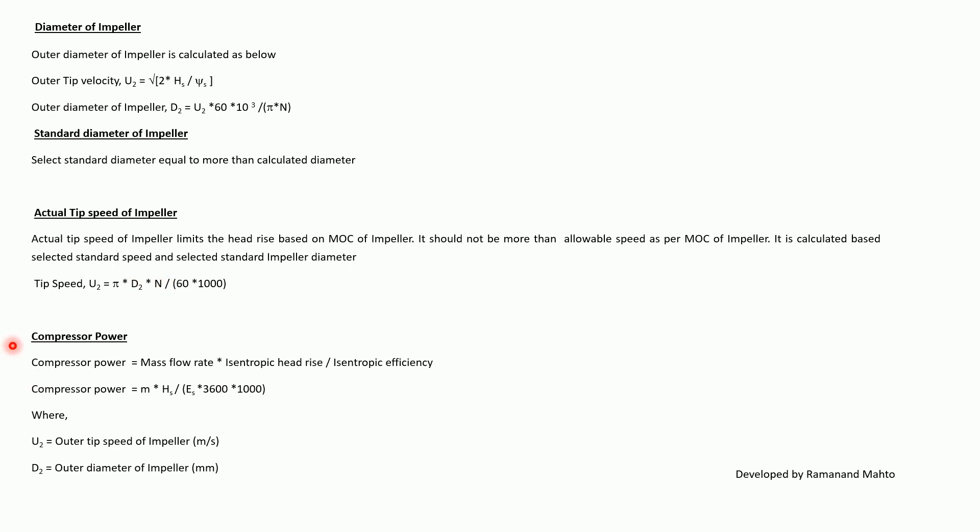Compressor power is equal to mass flow rate multiplied by isentropic head rise divided by isentropic efficiency. Compressor power = M × HS / (ES × 3600 × 1000), where U2 is the outlet tip speed of the impeller in m/s and D2 is the outlet diameter of the impeller in millimeters.